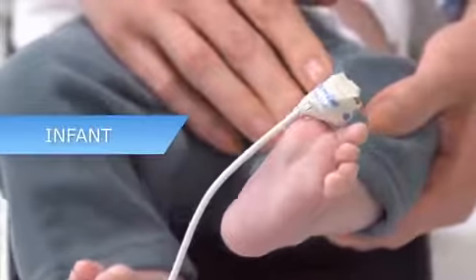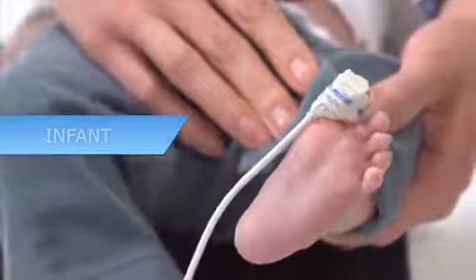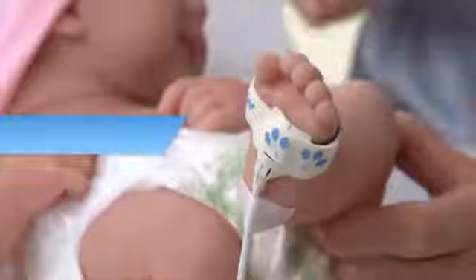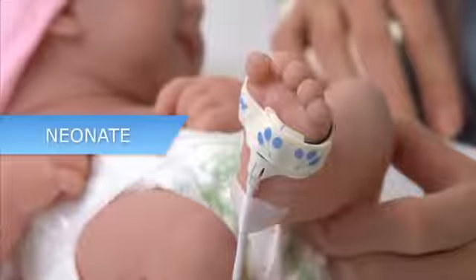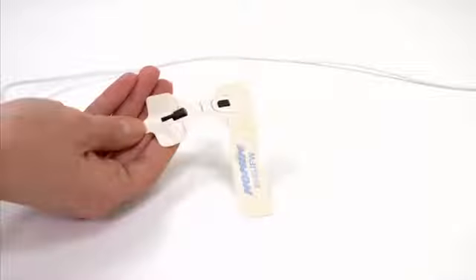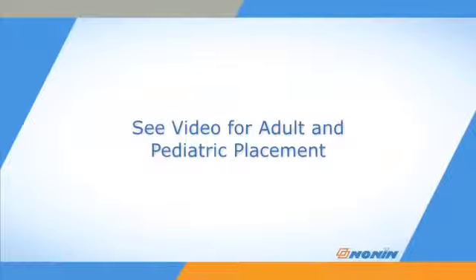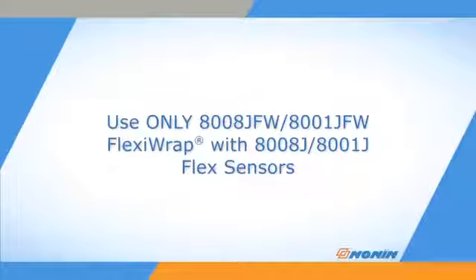The FlexiWrap is designed to secure the sensor in position on the large toe of infants, or the lateral foot of neonates up to 4 pounds, or 2 kilograms in weight. Several sizes may be used for adult and pediatric finger placement as well. Watch that video for a finger placement demonstration. These sensors should only be secured with the matching size FlexiWrap. Other adhesives or tapes will not properly position the sensor and may cause damage to it.